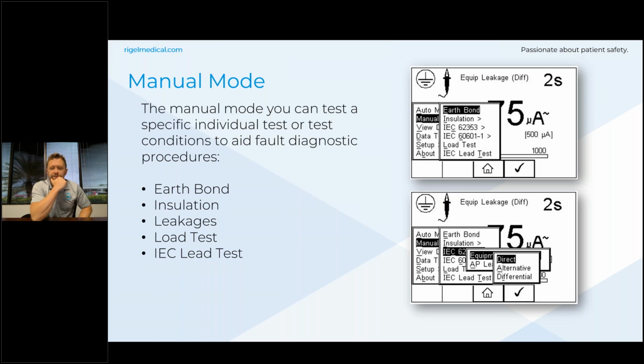And within our testers, if you look on a SafeTest, for example, with NFPA 99, that will switch to ground bond. But it's the same measurement. It does exactly the same thing. It's purely terminology.